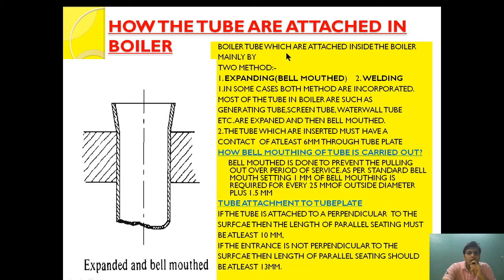Boiler tubes are attached by only two methods: expanding and welding. In expanding, we first expand the tube and then bell mouth it. In some cases both methods are incorporated — for example, in a smoke tube boiler, both bell mouthing/expanding and welding are carried out. Most tubes in the boiler such as generating tubes, screen tubes, and water wall tubes are expanded and then bell mouthed.